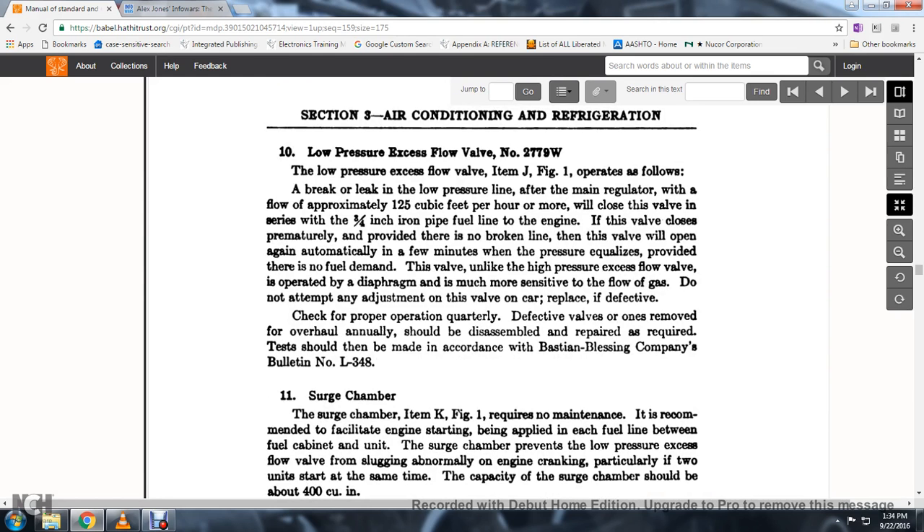Low-pressure excess flow valve No. 2779W: this valve, item J, figure 1, operates to close in case of a break or leak of low pressure line after the main regulator when the flow is approximately 125 cubic feet per hour more than normal, closing the valve. With a series of 3/4-inch iron pipe fuel line with the engine, if the valve closes prematurely and there is no broken line, it will open automatically in a few minutes when pressure equalizes, provided there is no fuel demand. This valve, unlike the high-pressure excess flow valve, operates with a diaphragm and is more sensitive to gas flow. Do not attempt to adjust the valve; if the car's valve shows improper operation, replace the defective valve. Quarterly inspections; defective valves should be removed, overhauled annually, and repaired as required.